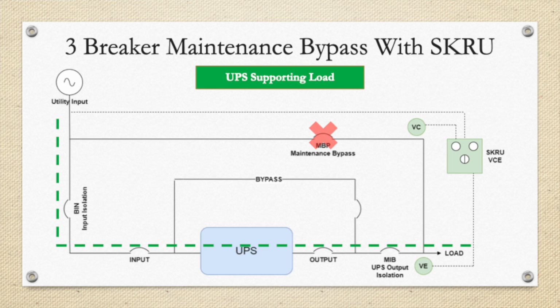Once you transfer the UPS to internal bypass, it will allow the release of the key or Kirk key lock on the maintenance bypass breaker, then will allow you to close breaker MBP and open breaker MIB, hence placing the load on external maintenance bypass. We're going to talk about SKRUs again on another drawing.